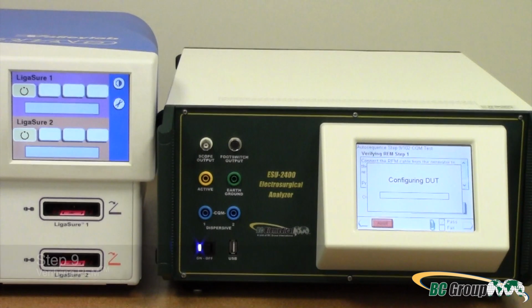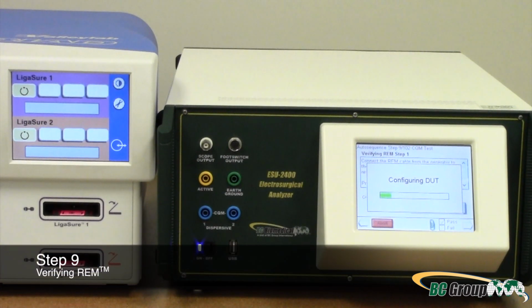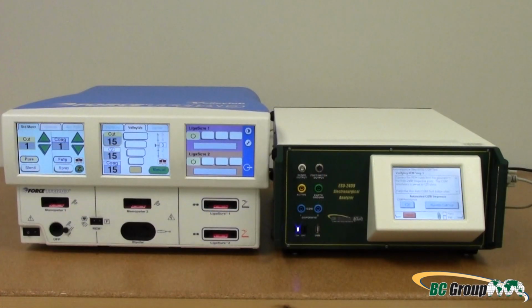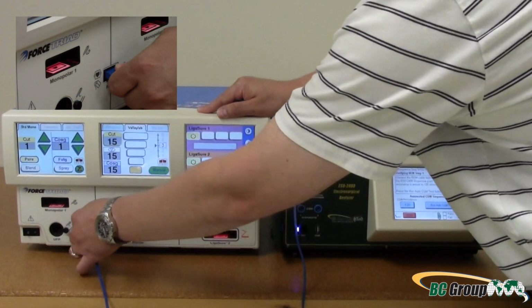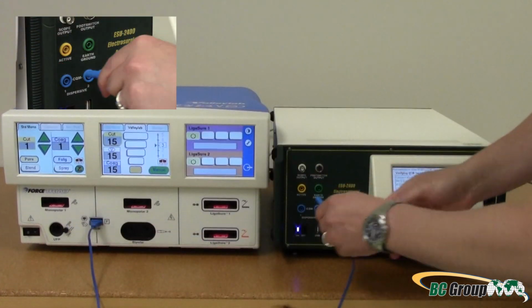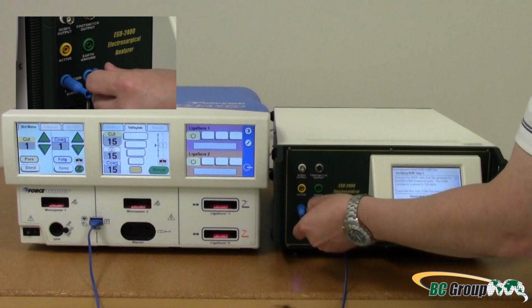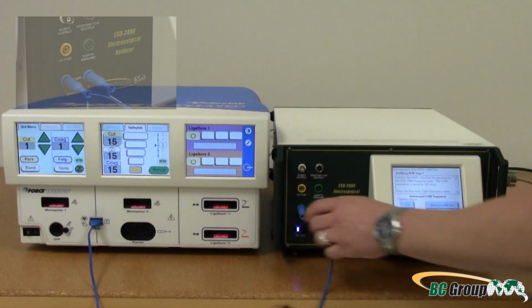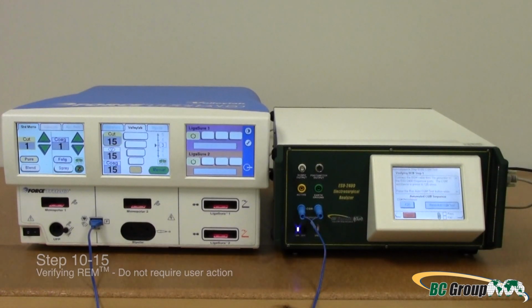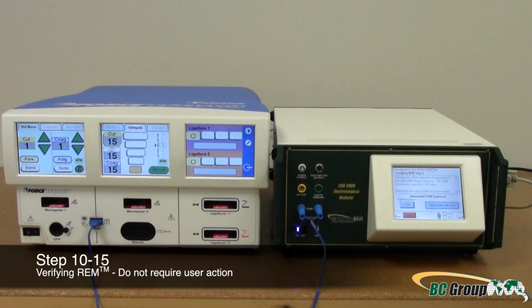Verifying REM. Step 9. Verifying REM. Connect the REM cable from the generator to the ESU-2400 dispersive ports. Then press the Run Autosequence Test button. Steps 10 through 15 do not require user action.